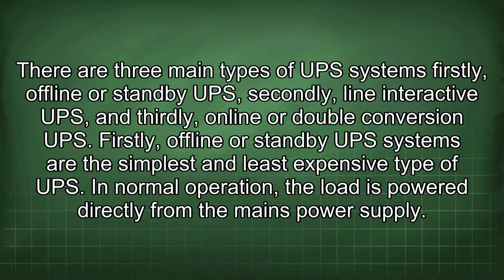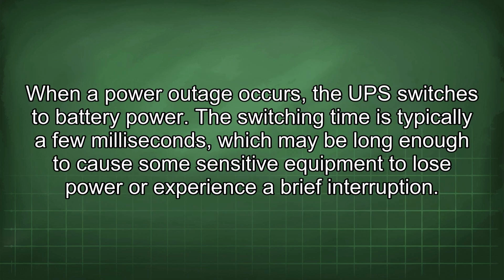Firstly, offline or standby UPS systems are the simplest and least expensive type of UPS. In normal operation, the load is powered directly from the mains power supply. When a power outage occurs, the UPS switches to battery power. The switching time is typically a few milliseconds, which may be long enough to cause some sensitive equipment to lose power or experience a brief interruption.